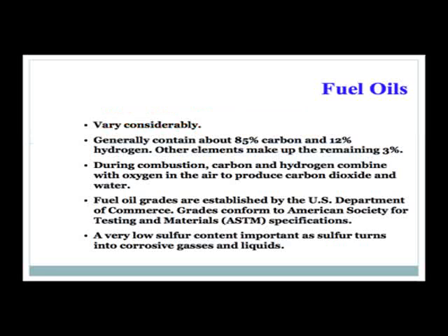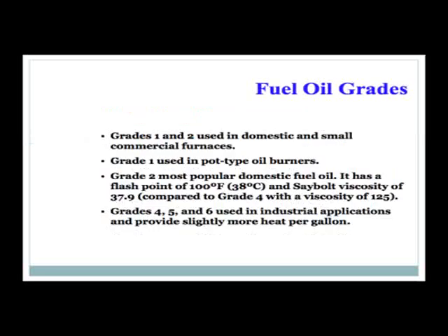Fuel oil grades are established by the US Department of Commerce, conform to the American Society for Testing and Materials specifications. A very low sulfur content is important because sulfur turns into corrosive gases and liquids. Grades 1 and 2 are used in domestic and small commercial furnaces. Grade 1 is used in pot-type oil burners, and Grade 2 is the most popular domestic fuel oil.